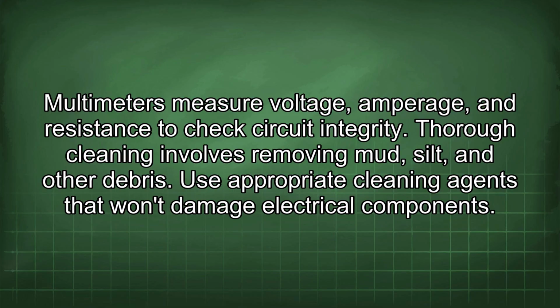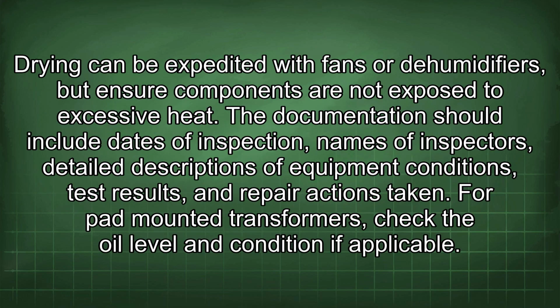Thorough cleaning involves removing mud, silt, and other debris. Use appropriate cleaning agents that won't damage electrical components. Drying can be expedited with fans or dehumidifiers, but ensure components are not exposed to excessive heat. The documentation should include dates of inspection, names of inspectors, detailed descriptions of equipment conditions, test results, and repair actions taken. For pad-mounted transformers, check the oil level and condition if applicable.